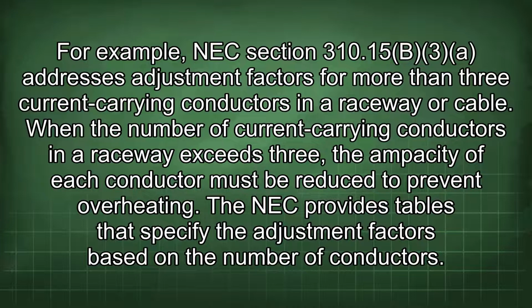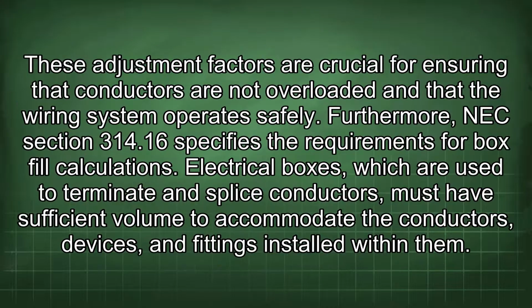For example, NEC Section 310.15(B)(3) addresses adjustment factors for more than 3 current carrying conductors in a raceway or cable. When the number of current carrying conductors in a raceway exceeds 3, the ampacity of each conductor must be reduced to prevent overheating. The NEC provides tables that specify the adjustment factors based on the number of conductors. These adjustment factors are crucial for ensuring that conductors are not overloaded and that the wiring system operates safely.